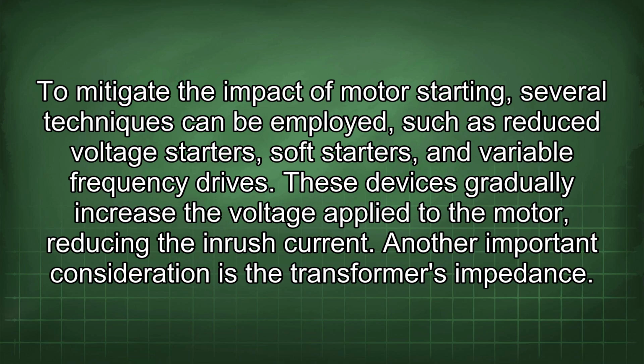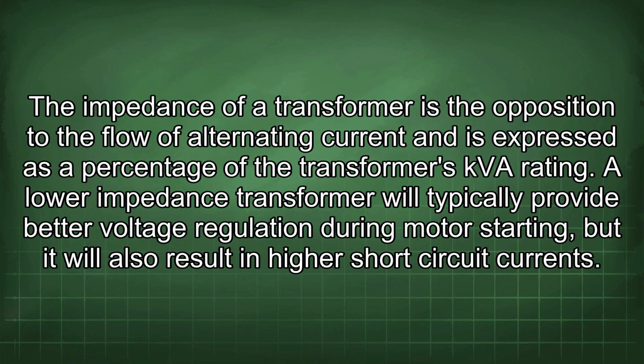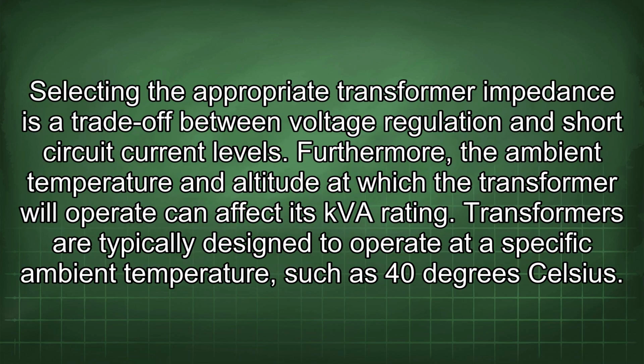Another important consideration is the transformer's impedance. The impedance of a transformer is the opposition to the flow of alternating current and is expressed as a percentage of the transformer's kVA rating. A lower impedance transformer will typically provide better voltage regulation during motor starting, but it will also result in higher short-circuit currents. Selecting the appropriate transformer impedance is a trade-off between voltage regulation and short-circuit current levels.